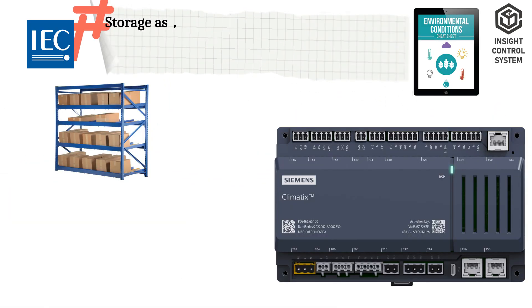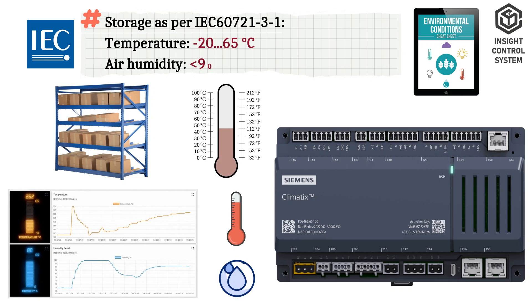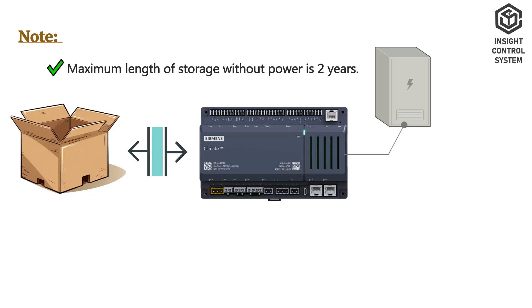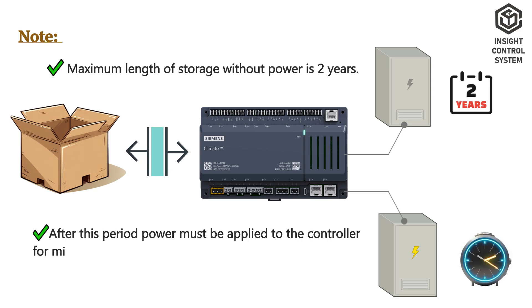Environmental compatibility — climatic ambient conditions in storage: temperature minus 20 to 65 degrees Celsius, air humidity less than 90% RH non-condensing. Note: maximum length of storage without power is 2 years; after this period, power must be applied to the controller for a minimum of 4 hours.